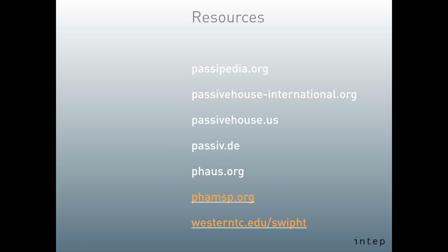Yes. So the question is, what's the capacity of the vent system, and the exhaust pickups are the return, as you said. It's a 300 cubic meters an hour unit nominal capacity, which is 200 CFM. The design airflow for the building is lower than that. I would say it's probably around 100, 120, something like that. I'm doing this from memory. Don't hold me to it.